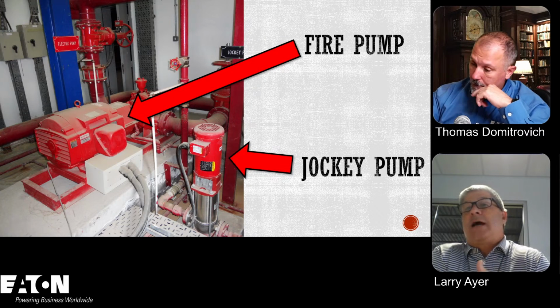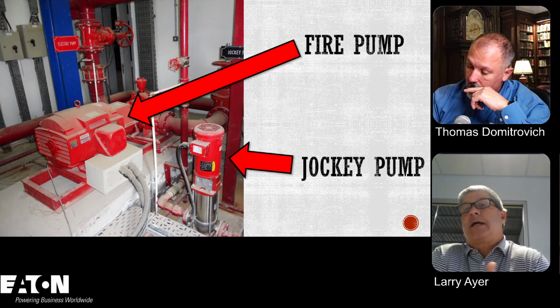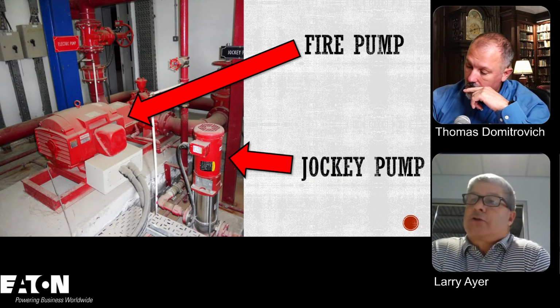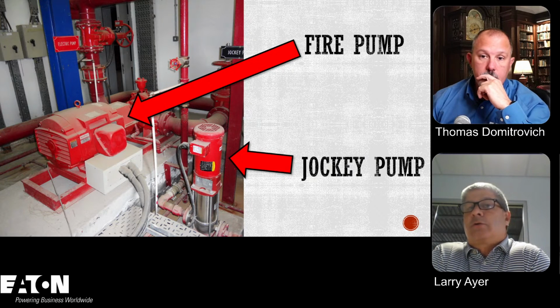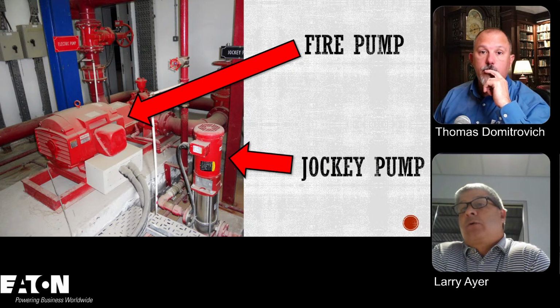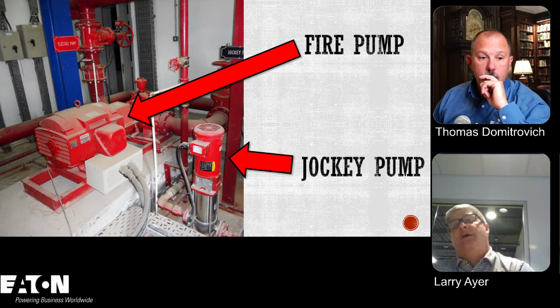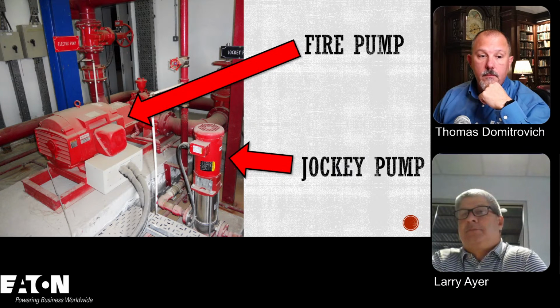So that way, if you happen to have a drop in pressure in the pipe, that will be able to send signals to the controller to let it know that you might have a leak, or that a sprinkler actually opened up and you need to do something. And then the fire pump and the controller need to alarm people.